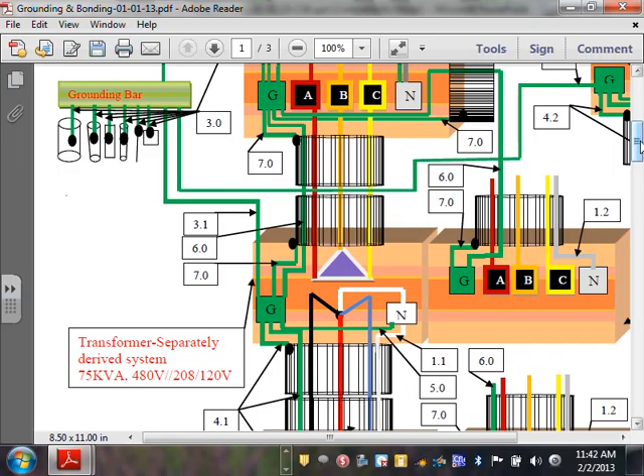A separately derived system, that's why we call it, it's like a new service. You have to go all the way. Now, does it work if you do it this way? I guarantee you it would. You know what I mean? For safety, they don't want the separately derived system grounding electrode to depend on the service. It goes all the way up to the grounding electrode system.